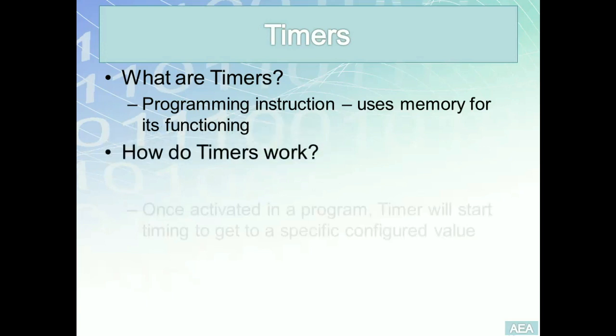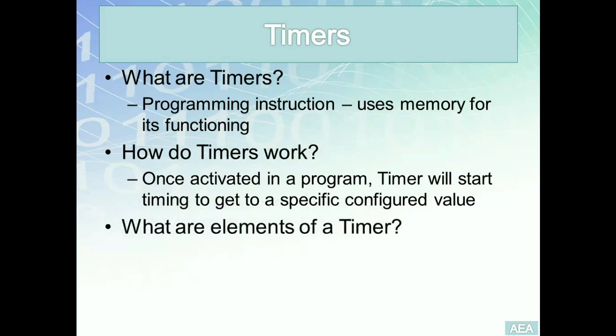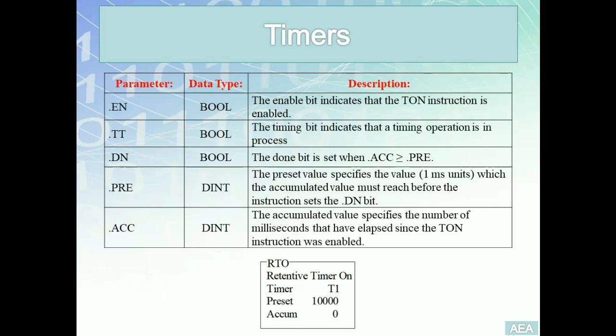Once a timer is activated in the program, it will start timing to reach a specific configured value. The parameters of a timer include two double integers — the preset value and the accumulator value — and three Boolean parameters: the enable bit, the timer timing bit, and the done bit. Having a good understanding of all these parameters will enable us to successfully integrate a timer into our solution.